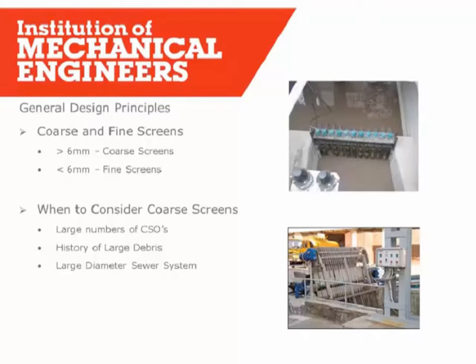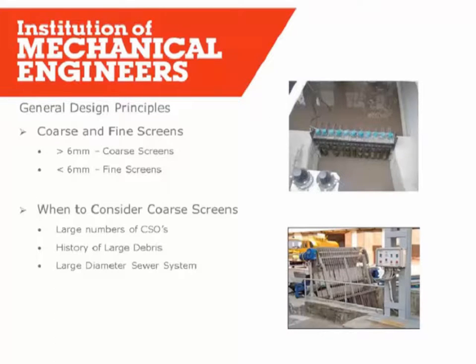On to general design principles. There are two main types of screen: coarse and fine. We define coarse screens as those with an aperture greater than six millimeters, and fine screens as those with less than six millimeters in two dimensions. Generally speaking, if you install coarse screens it's going to be more expensive - you're paying for more plant, a larger civil footprint, and increased maintenance. Consider coarse screens when your catchment has a large number of CSOs passing forward a lot of screenings to the fine screens - you may need coarse screens to protect them - or if you've got a large diameter sewer capable of passing large debris that could damage a fine screen.